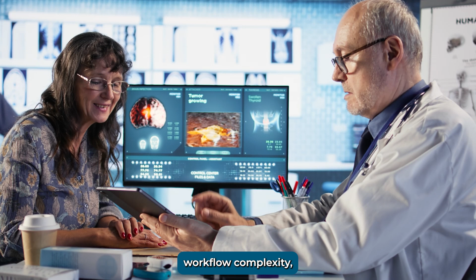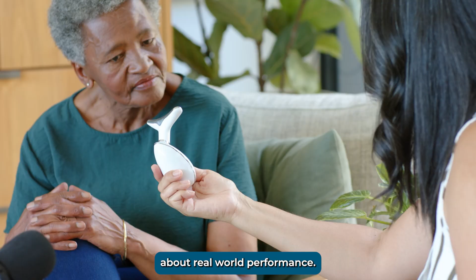A strong CAPA connects directly to risk management. If the failure can affect safety, performance, sterility, usability, or compliance, then the risk file must be reviewed. Severity, probability, detectability, residual risk, and existing controls may all need to be updated. A CAPA that never touches the risk file is often incomplete, because the device has just taught you something important about real-world performance.